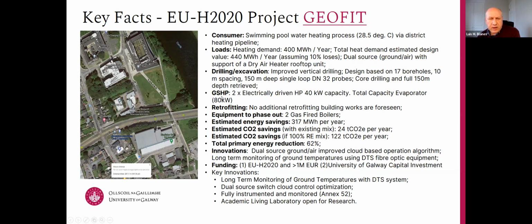We have two heat pumps of 40 kilowatts each at the evaporator capacity, delivering approximately 100 kilowatts base load to the swimming pool. We are hoping to replace the gas-fired boilers and the whole gas load of the existing heating system of the swimming pool. There are a number of initial calculations for savings, including CO2 savings.